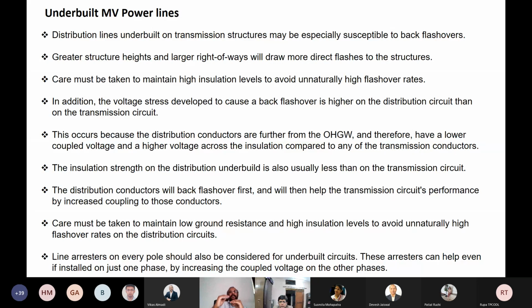Now you will understand that in HV lines, the insulator length will be quite a bit higher. For example, if you take a 400 kV HV line, the insulator length is much higher than in the case of a 33 kV medium voltage line. So the same voltage increment will be seen on the HV line and the MV line when it is underbuilt, but the backflashover possibility is much higher in the medium voltage line. So you have to pay special attention to that.